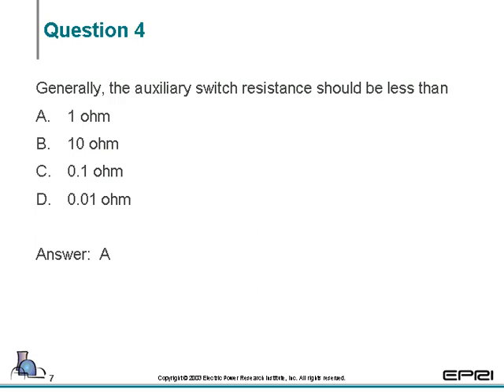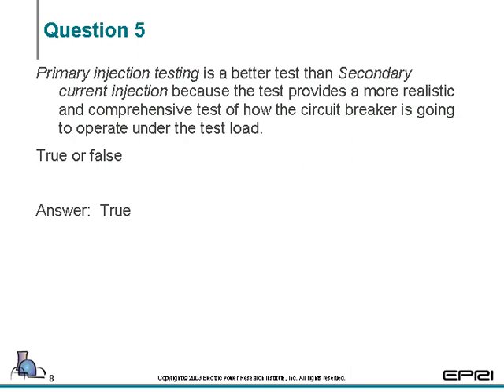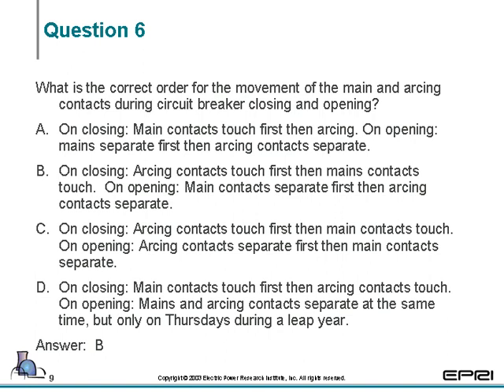Question 4. Generally, the aux switch resistance should be less than. The answer is A, 1 ohm. Gene covered that, I think at least once in the presentation, maybe twice. Question 5, primary injection testing is a better test than secondary current injection because the test provides a more realistic and comprehensive test of how the circuit breaker is to operate under the test load. That is true. It tests the CTs, and the polarity, and the wiring, and the overcurrent trip device, where the secondary current injection only tests the trip device. So the answer is true.